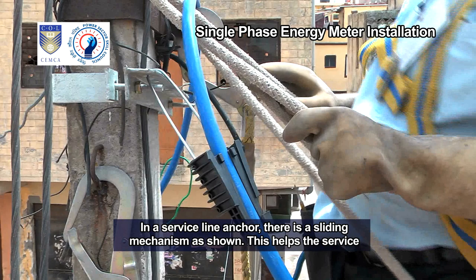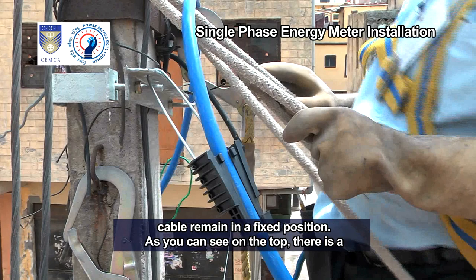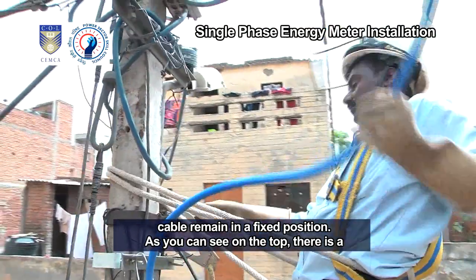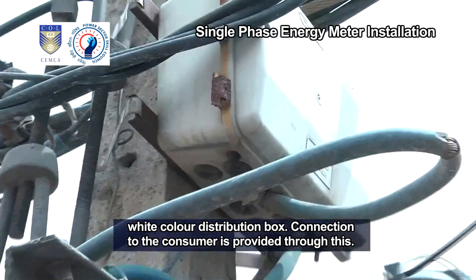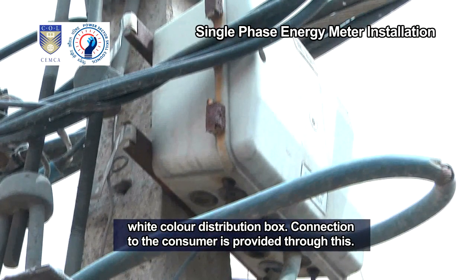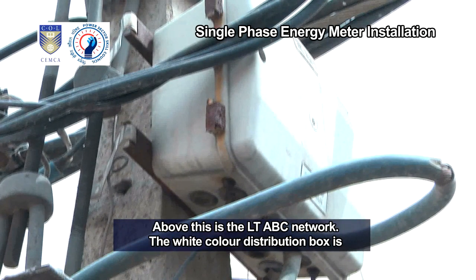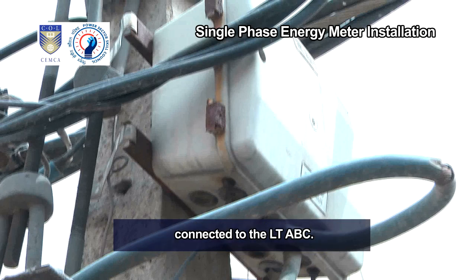In a service line anchor, there is a sliding mechanism as shown. This helps the service cable remain in a fixed position. As you can see on the top, there is a white color distribution box. Connection to the consumer is provided through this. Above this is the LT-ABC network. The white color distribution box is connected to the LT-ABC.